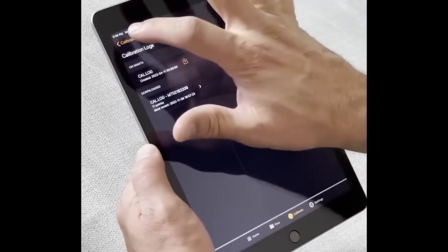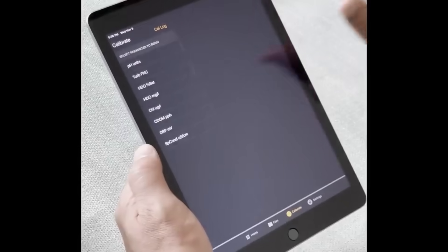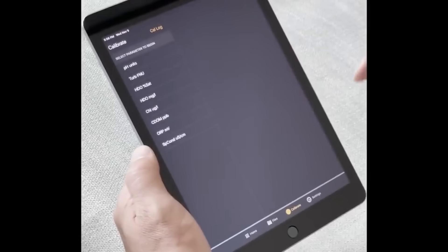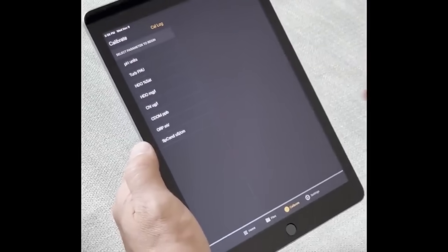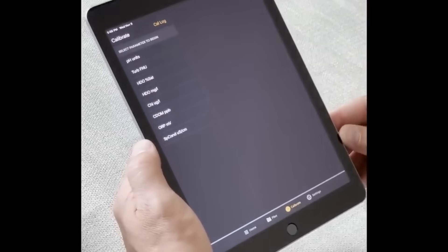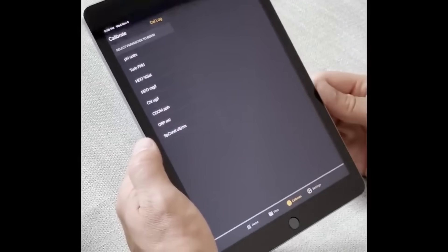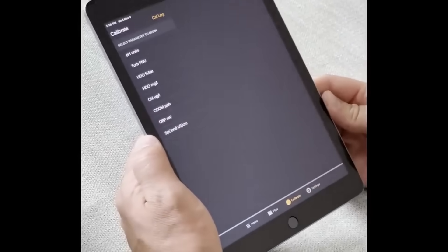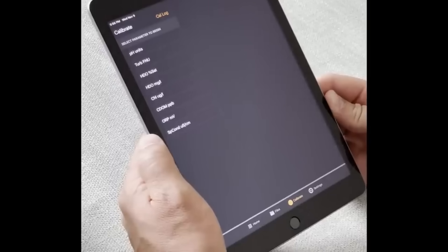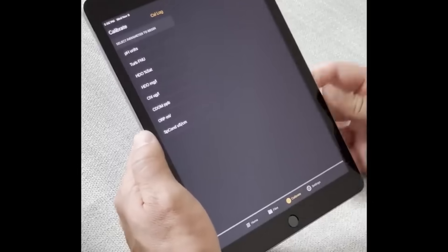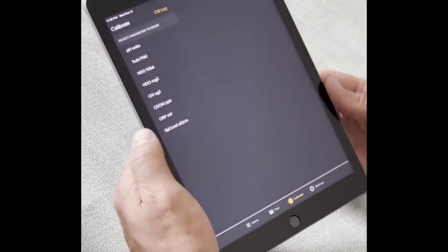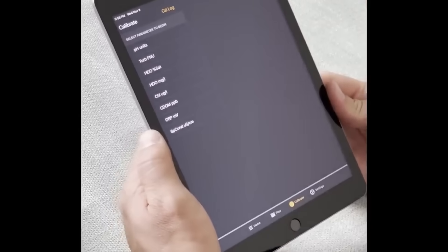I'm going to cancel that and go back. Arrow back to calibrate. If you were to calibrate your next parameter, you can select from this selection here, and it will walk you through that calibration process like you just saw.